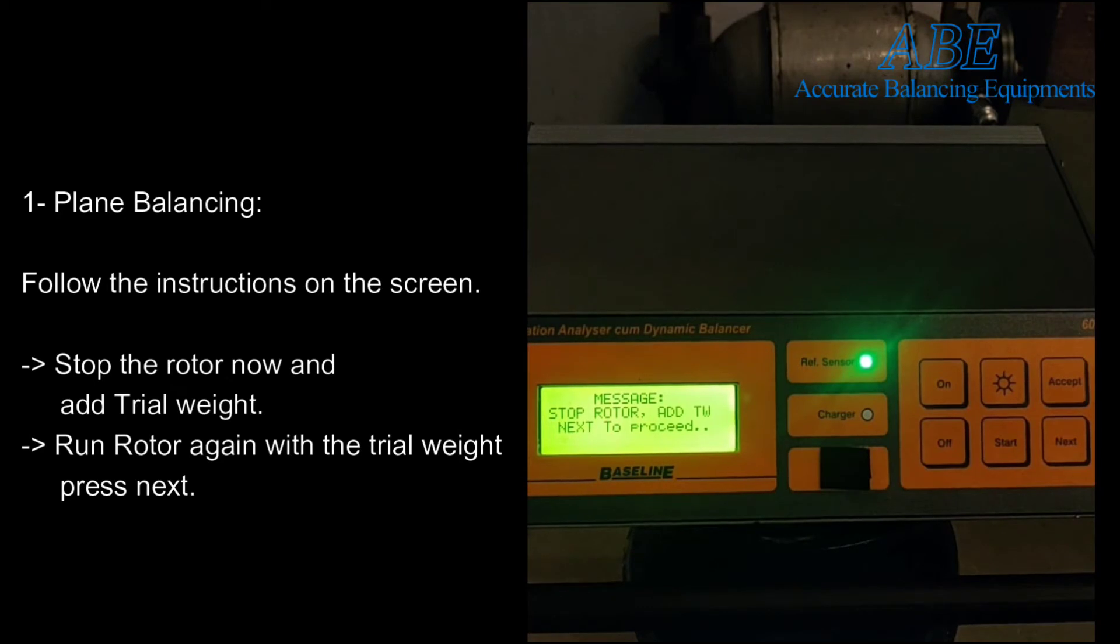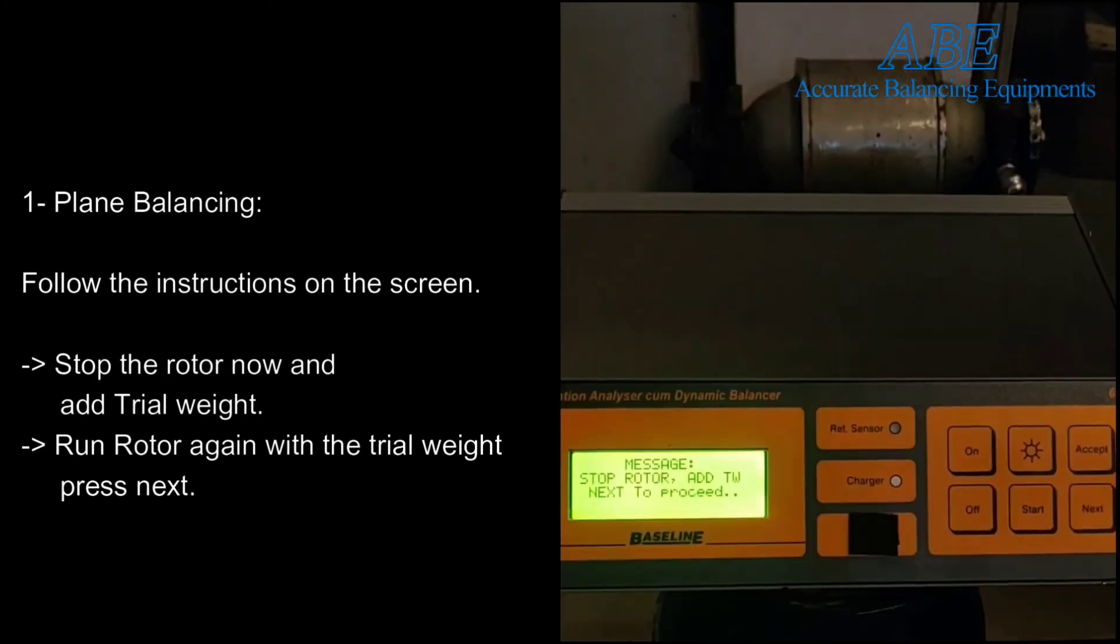A sharp auto-tracking filter synchronizes automatically to the rotational speed and filters out all extraneous vibrations. It is also possible to compare the overall and synchronous vibration readings to confirm unbalance as being the dominant cause of vibration.